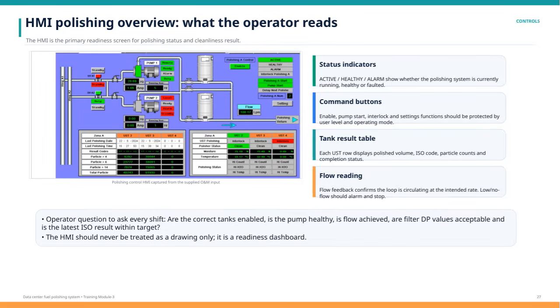On this slide, we focus on the HMI polishing overview, specifically what the operator sees and how it guides their actions. The HMI serves as the main readiness screen, showing the current status of the polishing system and cleanliness results in real time. First, the status indicators are crucial. They tell us if the system is active, running smoothly, or if there's an alarm signaling a fault. These indicators help the operator quickly assess the system's health at a glance.